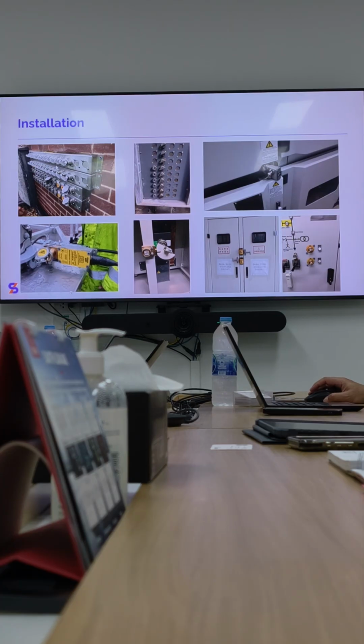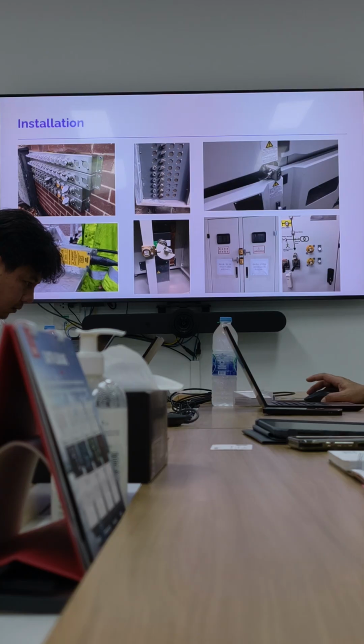This one is usually used in coal power plants. After burning the coal, the fuel goes to a filter, called a static precipitator filter. When they need to do maintenance, that filter system has many doors, maybe 10, 20, 30 doors, because it's very long. So they isolate the main power, come here to pick up all the keys for all the doors, and do the maintenance. As long as one of the keys or doors is not locked and the key cannot come back, the main power cannot open, cannot close, cannot energize. This prevents someone doing maintenance while another guy energizes it and leaves.